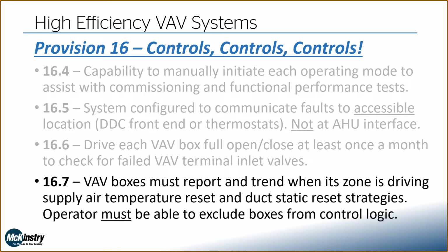And your VAV boxes have to tell the system when its respective zone is driving our temperature and duct static reset strategies. So usually you end up with one or two boxes that are the worst offenders, and they're kind of driving everything else. And your system has to be able to report and trend when that is happening for every VAV box. And the operator has to be able to exclude those boxes from the logic. They don't have to exclude them, but they have to be able to if it's causing a problem with the rest of the system.